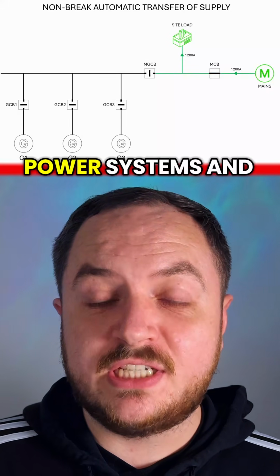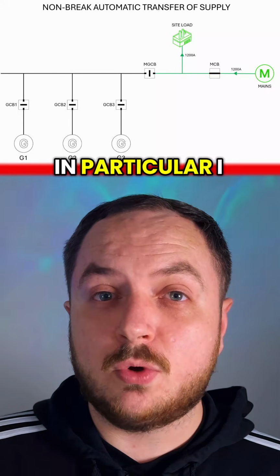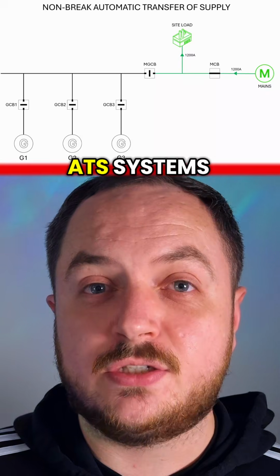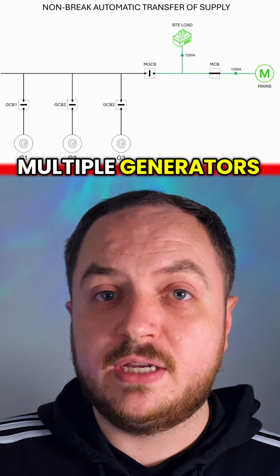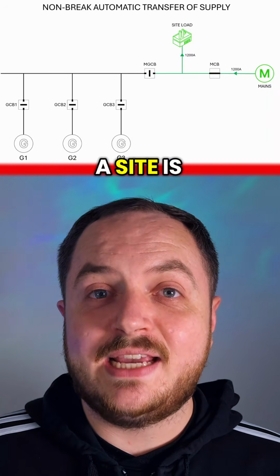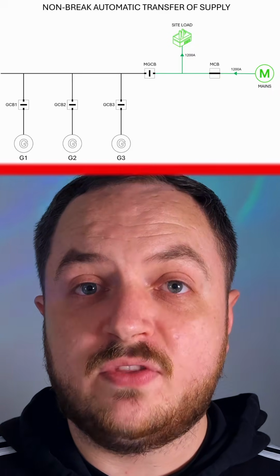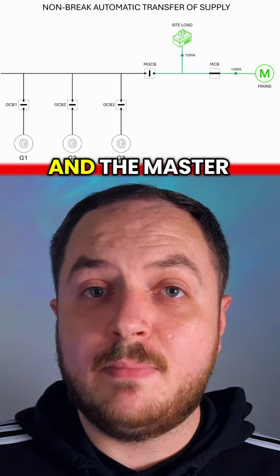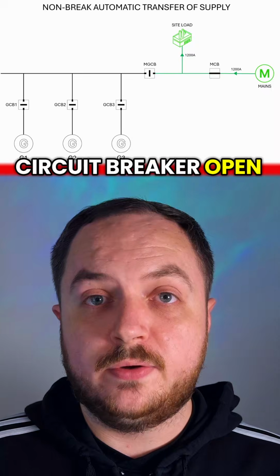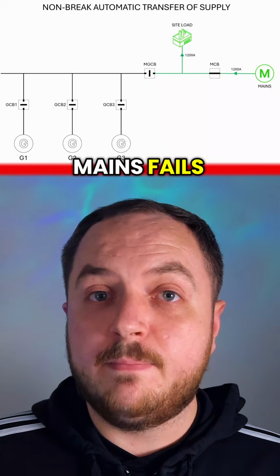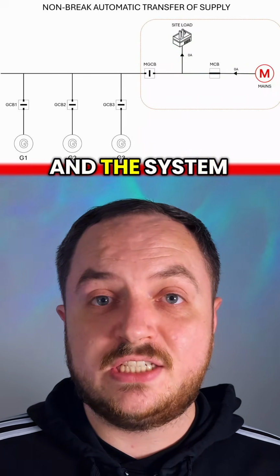Let's talk about power systems and synchronizing. In particular, I want to talk about synchronizing ATS systems with one mains and multiple generators. So under normal conditions, a site is powered by its main supply with the main circuit breaker closed and the master generator circuit breaker open.